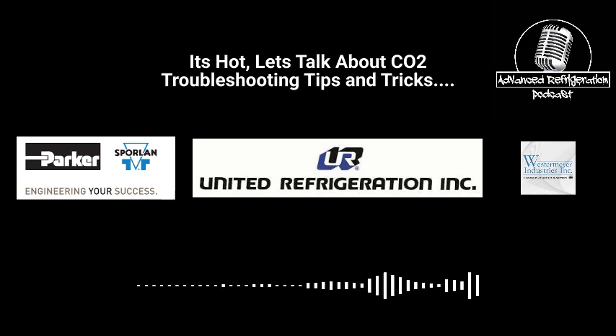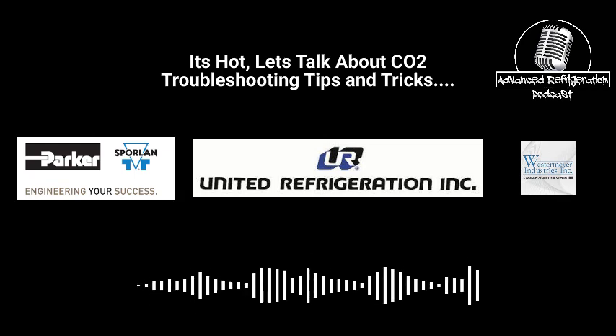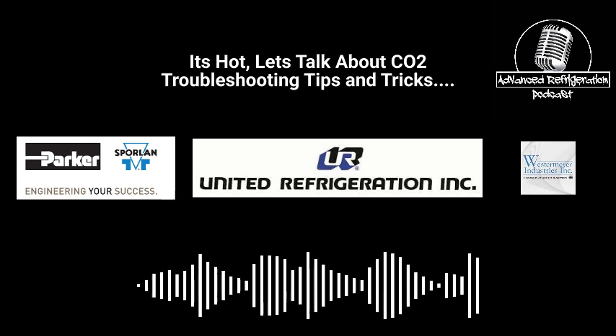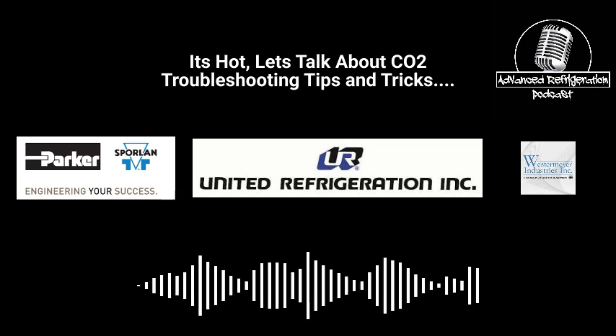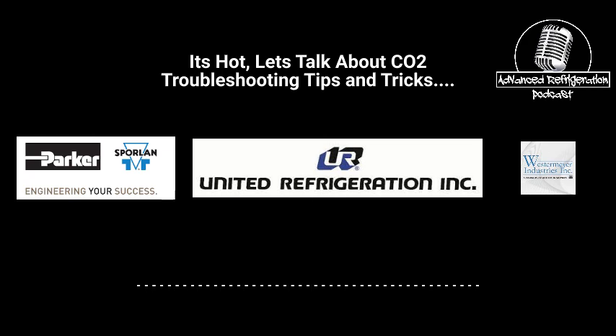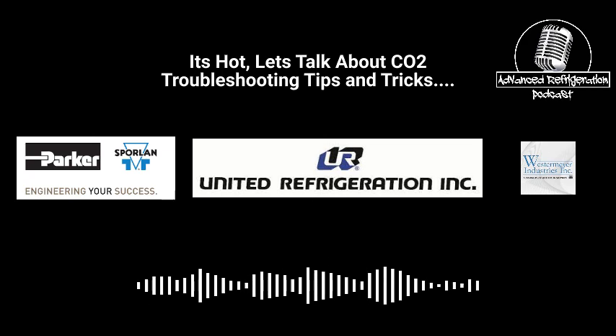Yep. Every time we have a rack with a dual separator issue, it's not every week, it's not every month, but there's a time or two where the oil all gets stuck in the medium temp or all gets stuck in the low temp. And the rack goes down and then somebody has to go out there and get it to transfer. That leads us into what else we were going to talk about, the oil sensors.